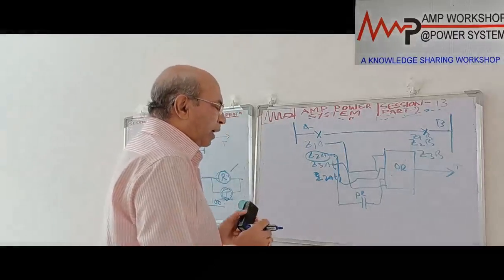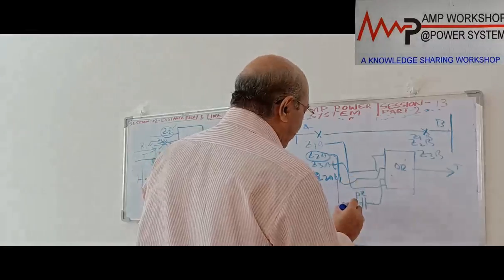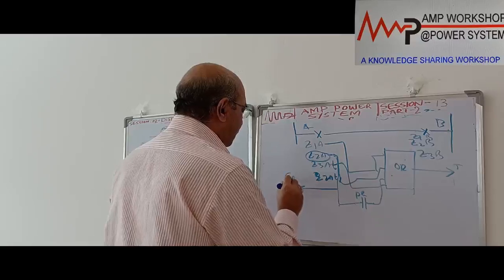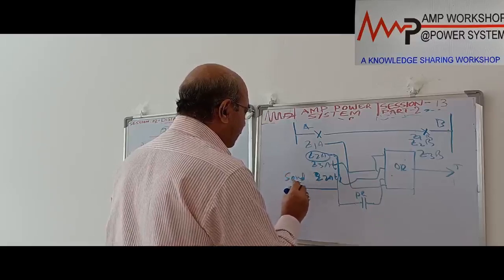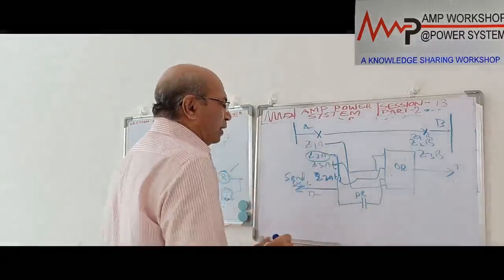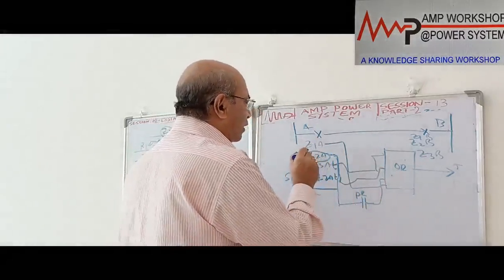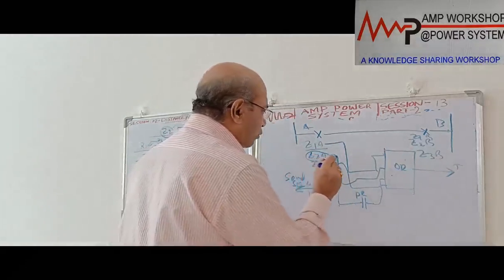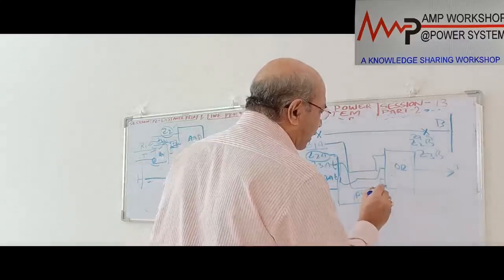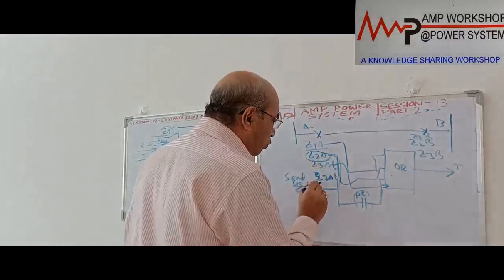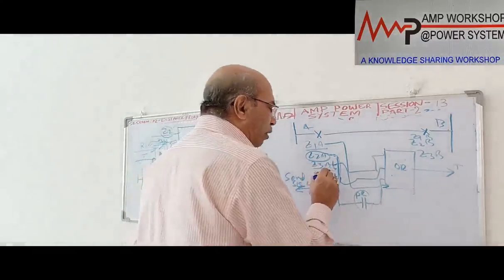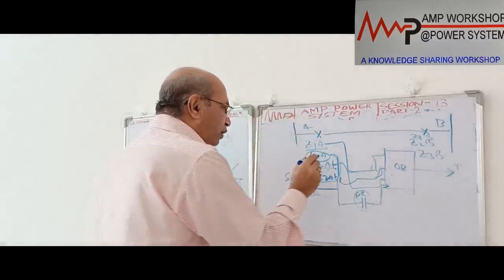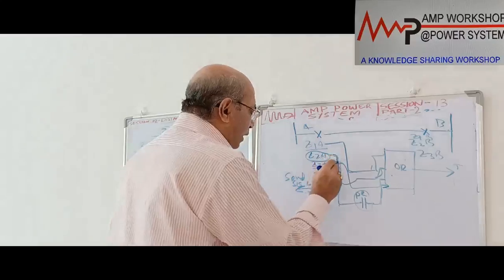Okay. Now here, at the same time, this Z2 element is issuing the send signal to the transmitter for this end, right? So this is the tripping logic. Zone 1 element gives instantaneous tripping. The zone 2 element, with a permissive, gives instantaneous tripping. Zone 2T normal time delay and zone 3T normal time delay also give the tripping command. These are the 4 tripping commands.